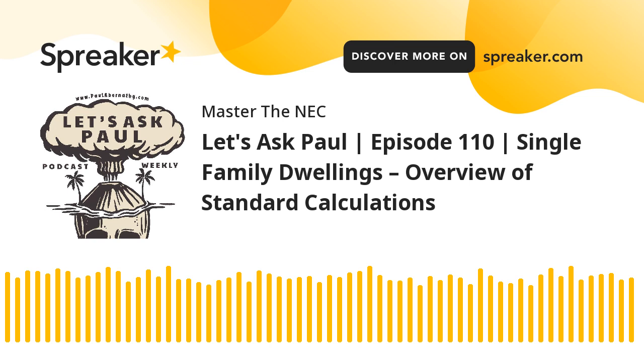Now, here's something interesting. If you were comparing heat versus AC in the previous step that we did, and the AC overtook the heat because you used that 125% for the air conditioning compressor, and that was what overtook the heat, then guess what? That 25% for the largest motor has already been taken care of. So you've already satisfied 220.50, so you don't have to go searching for the largest motor at that point, right?